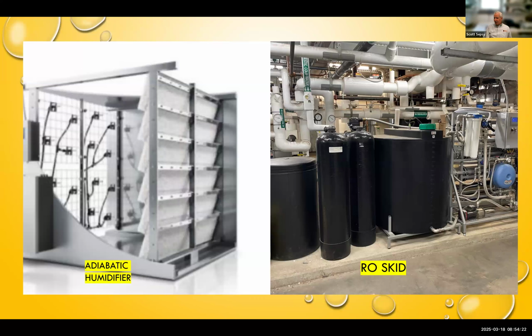But absorption distances may be longer with these adiabatic systems, so you've got to have room in the air unit. The absorption pads, which show here on the left, absorb the droplets and give the air another chance to reabsorb the water off the pads. Now, the grid with the humidifiers are run by solenoids, and they're just operated in different steps, with nozzles.